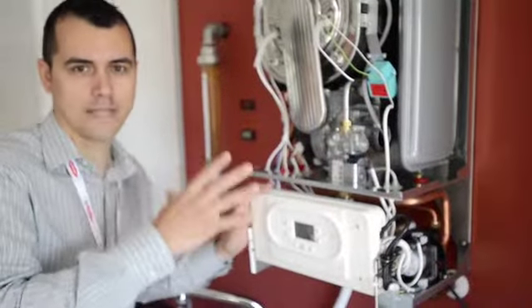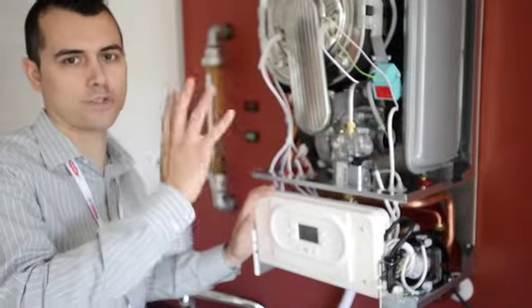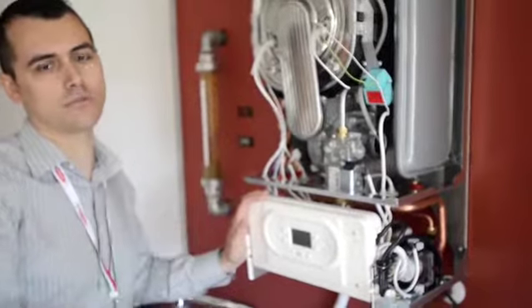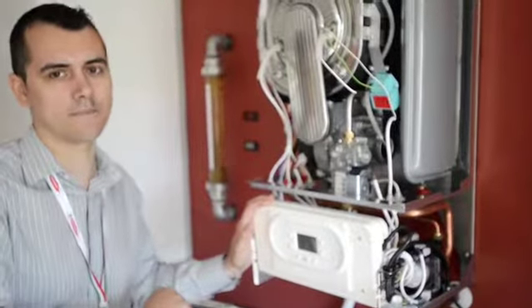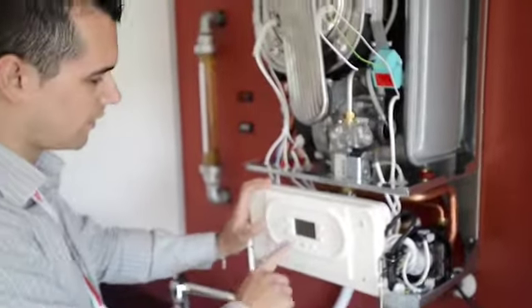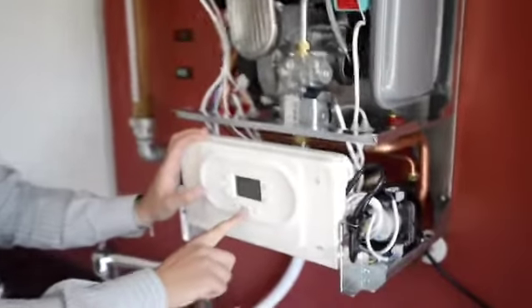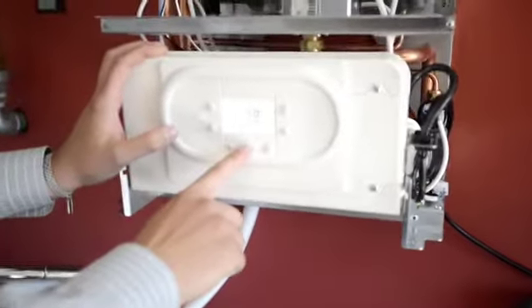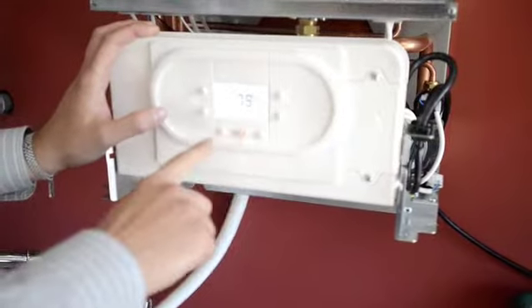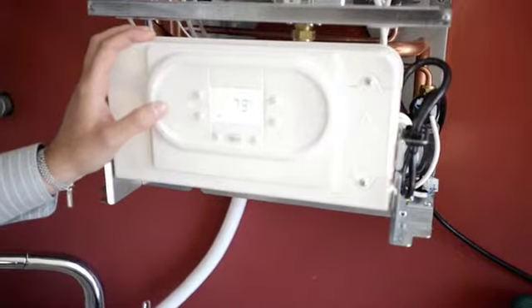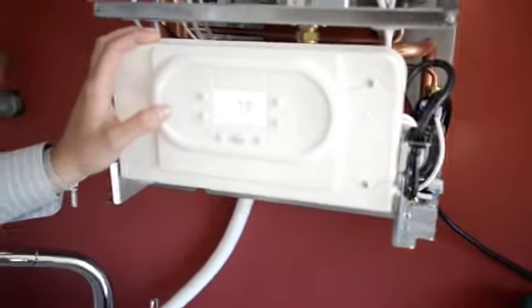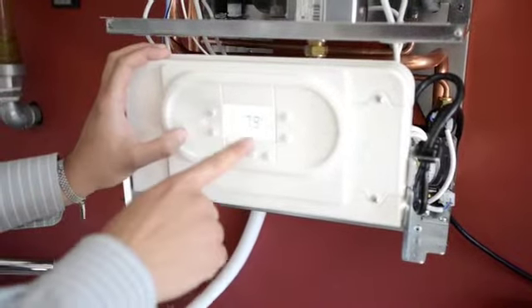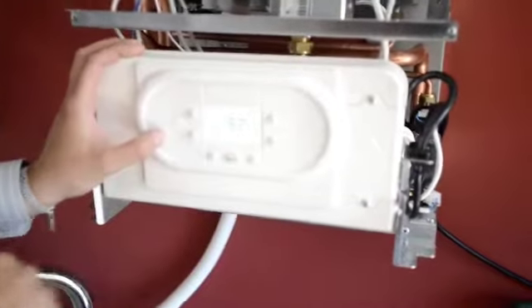One of the most important tests you will need to perform on the entirety of the condensation line is the CO2 test with the use of an analyzer. This is how we proceed. We turn on the heater by pressing the middle button. We put it in heating mode and we will see that the heater turns on, as we can see by the flame icon on the display.